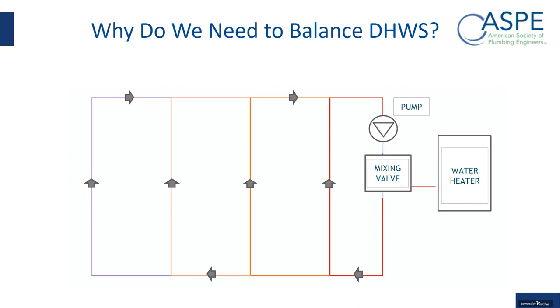As you move from the right to the left, the resistance to flow increases and the heat loss increases because the length of the pipes is increasing. When you get all the way out to the left, you're getting very little flow, if any, a high resistance to flow, and very high heat loss. So the water temperature here, if you turn on a fixture without balancing, would be very cold, if existent at all.